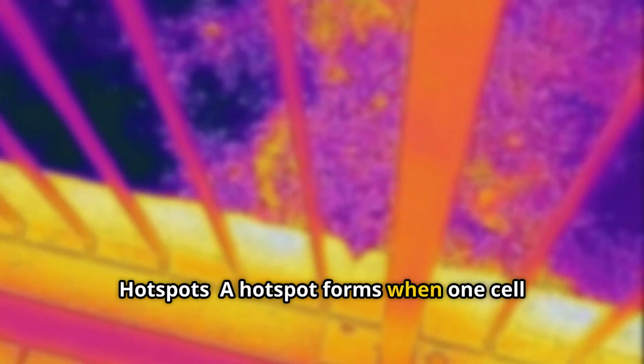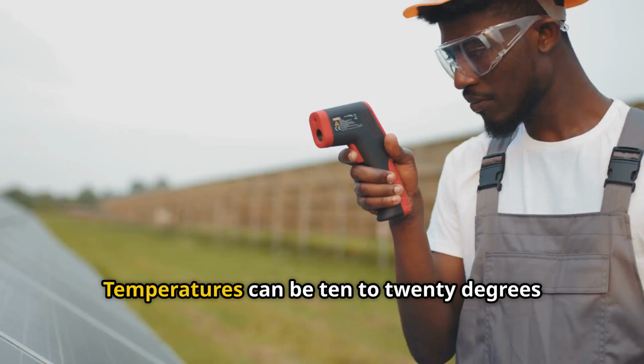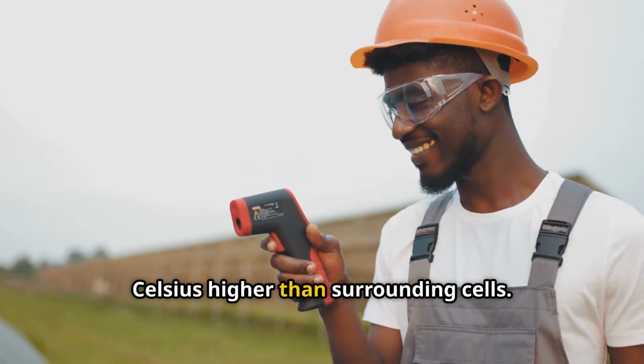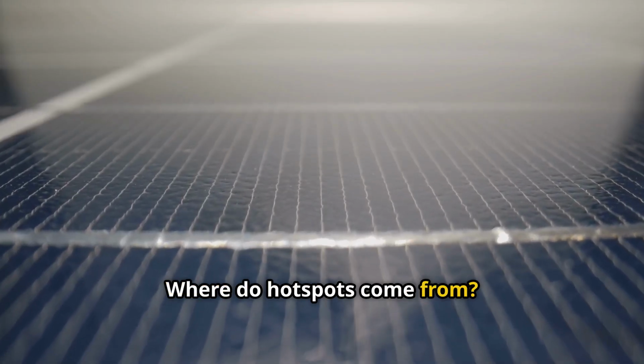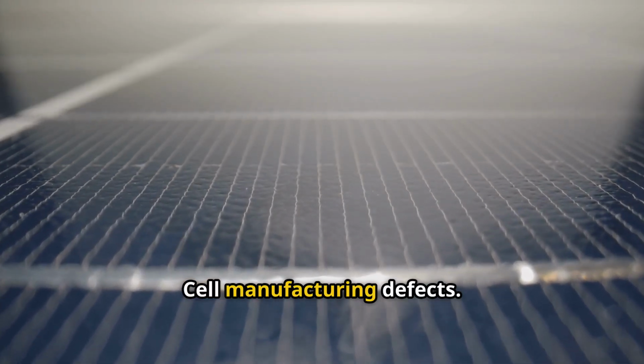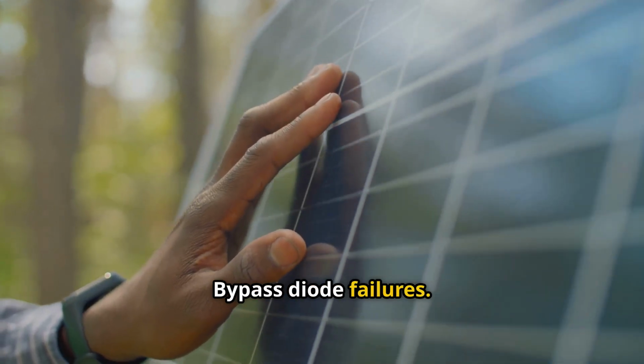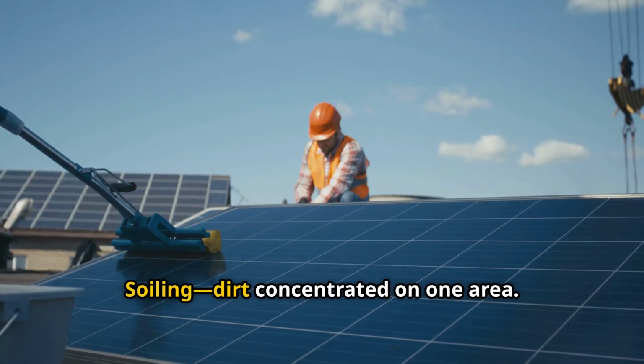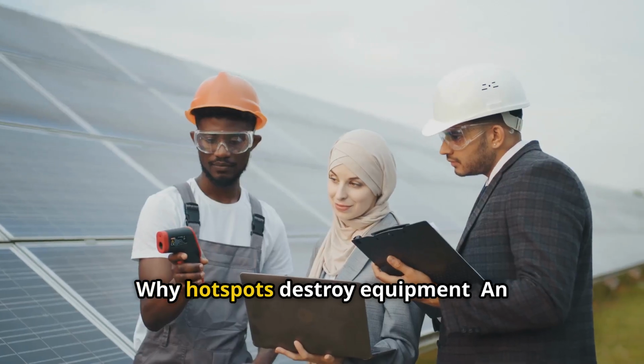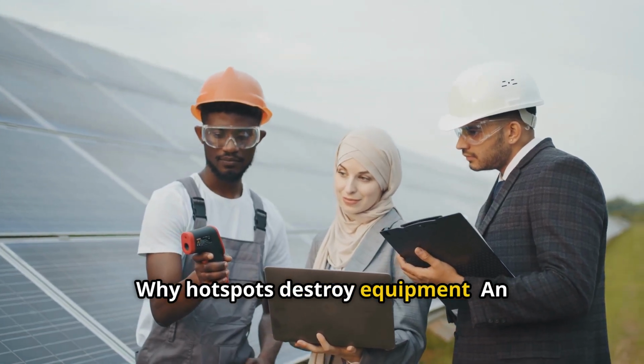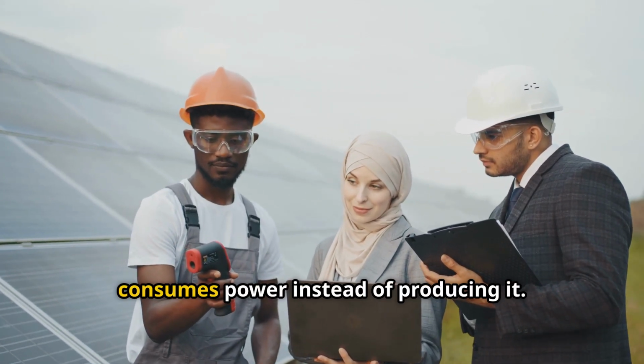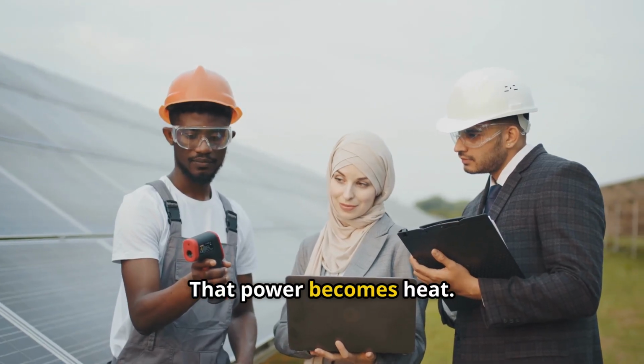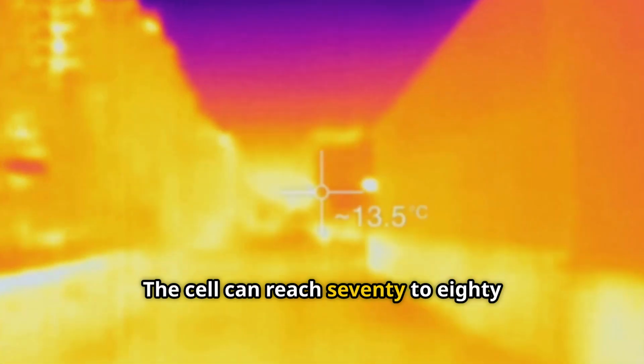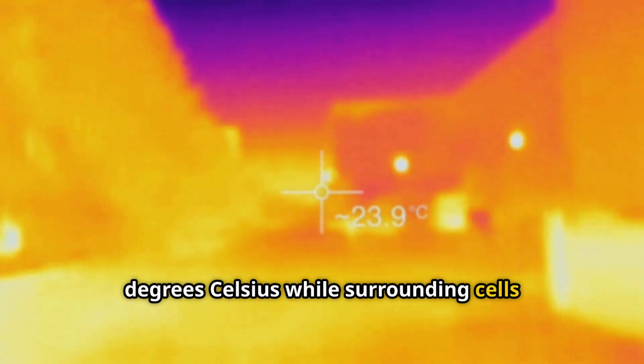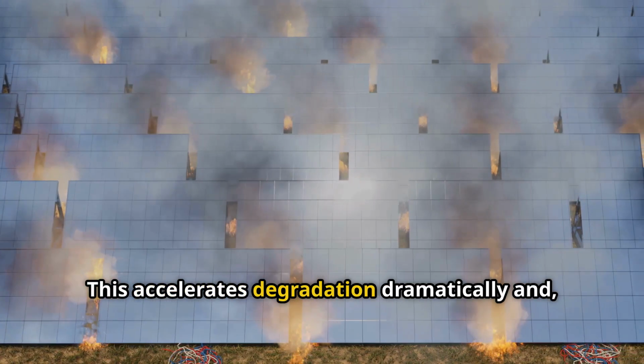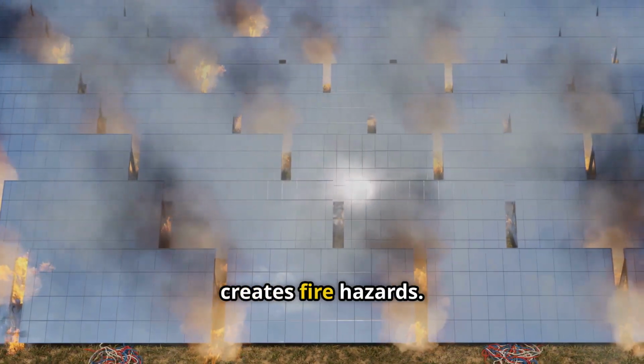Hotspots. A hotspot forms when one cell operates significantly hotter than its neighbors. Temperatures can be 10 to 20 degrees Celsius higher than surrounding cells. Where do hotspots come from? Shading, even partial. Cell manufacturing defects, bypass diode failures, internal resistance problems, soiling, dirt concentrated on one area. Why hotspots destroy equipment: an overheated cell becomes a resistor. It consumes power instead of producing it. That power becomes heat. The cell can reach 70 to 80 degrees Celsius while surrounding cells are at 50 degrees. This accelerates degradation dramatically and in extreme cases creates fire hazards.